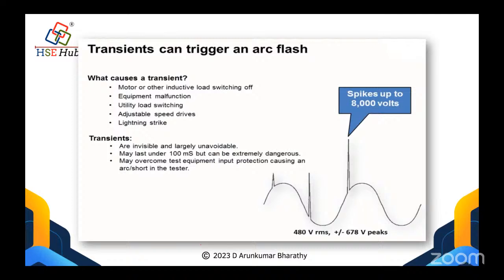Whenever we switch a inductive load on or off, or when any equipment malfunctions, it can create a transient. Utility load switching, like cooling towers and other utility loads, can also create some transient. And adjustable speed drives, which you will have in many process industries, and lightning strikes. These are the reasons a transient may trigger an arc flash. It can go up to 8,000 volts, 10,000 volts, and 15,000 volts, right? This is all invisible, and it may last under 100 microseconds, but it can be extremely dangerous.